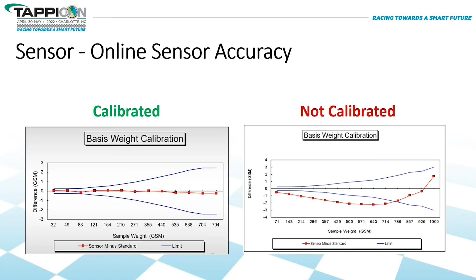So it's important to make sure the online sensor is calibrated first, and calibration should be done before correlation. Also, I want you to know that a calibrated sensor doesn't mean it's a correlated sensor. Next, let's take a look at the process. Many mills use the single point dynamic correlation method to correlate the online sensors with the lab.